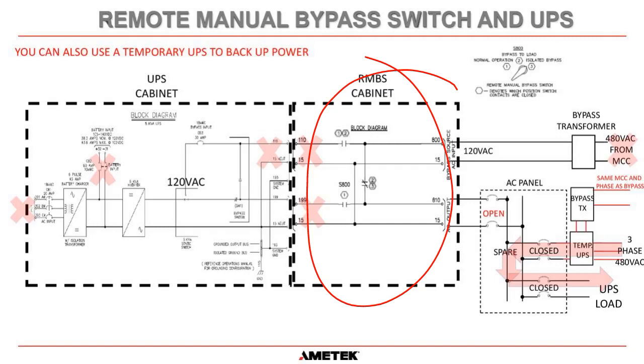Yes, you can. The RMBS really doesn't have any logic controls that go to the UPS itself. You can have some auxiliary contacts that tell the UPS what position the RMBS handle is in, but that's not necessary. In truth, just for being able to isolate the UPS, you can use an AMETEK Solid State Controls RMBS on a different model of UPS, as long as it matches the kVA rating and the output voltage rating. There are no proprietary connections that need to be done with our remote maintenance bypass switch. So it's very, very flexible to allow plants to do what they need to do.